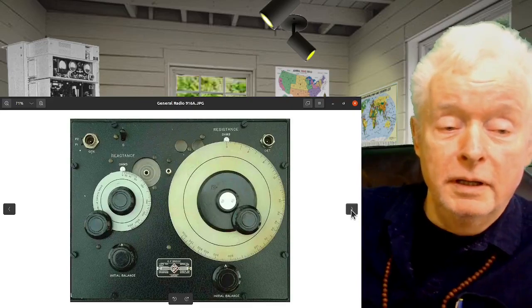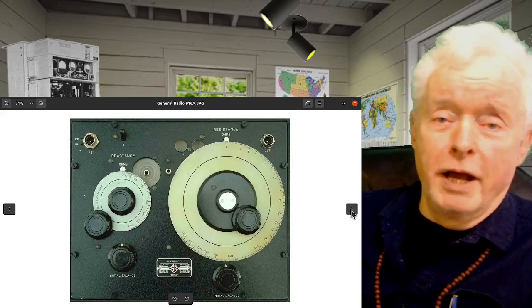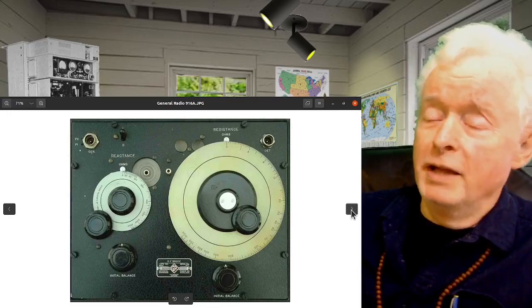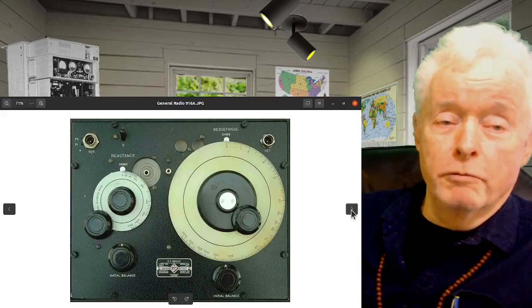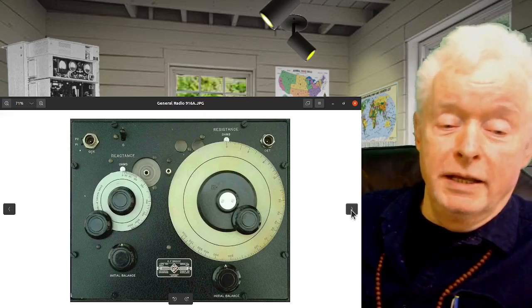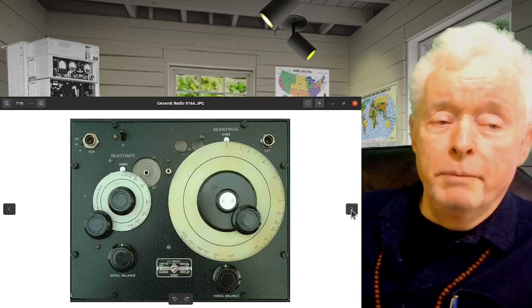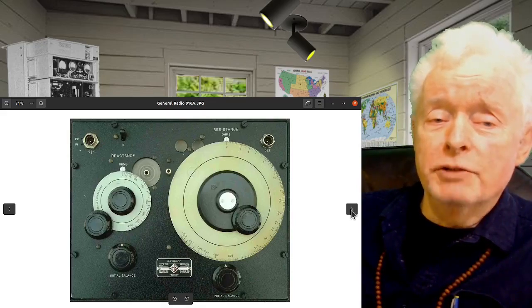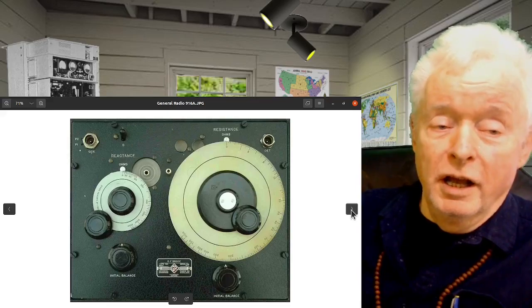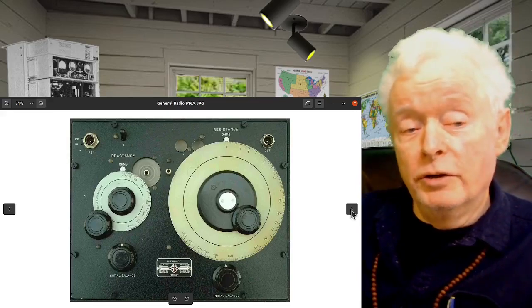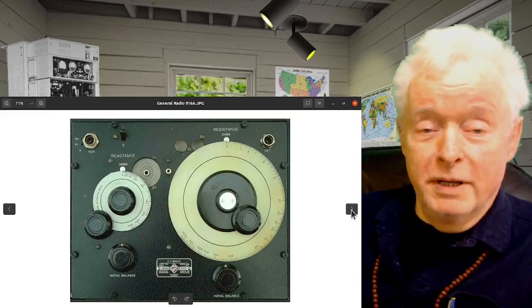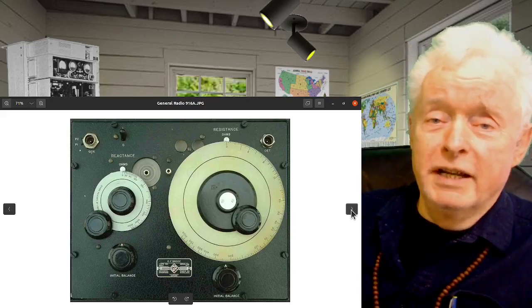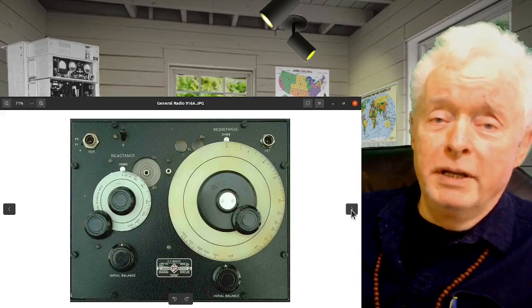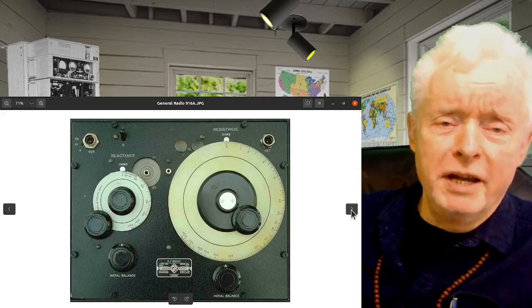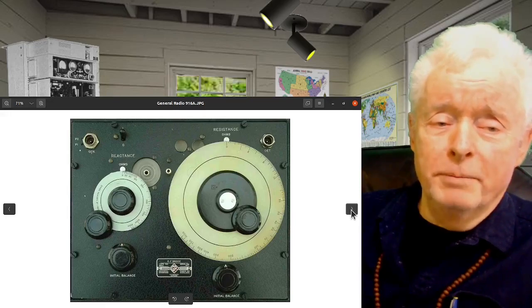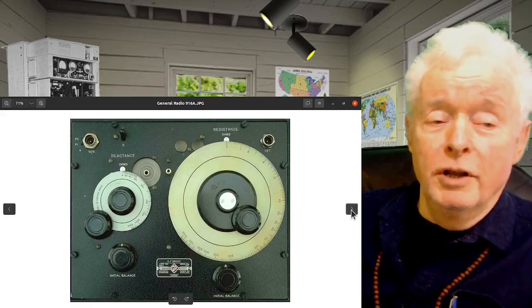So let's move on. Now this is one that you're not likely to have on your bench. This is for advanced users only. This is the General Radio 916A. It's a bridge for measuring the reactance, resistance, the impedance, of an element that is connected to the face of this instrument. They don't want to dilly-dally around with stray leads upsetting the balance. So you have to have something that connects smack dab right.